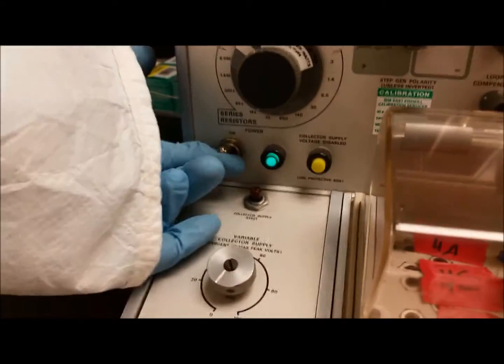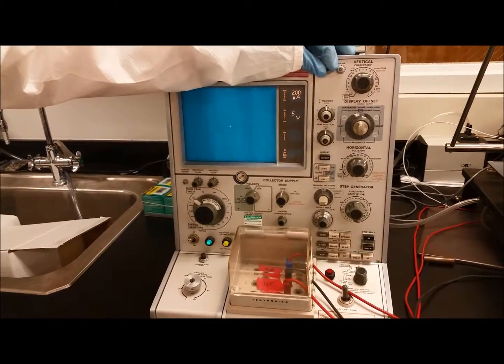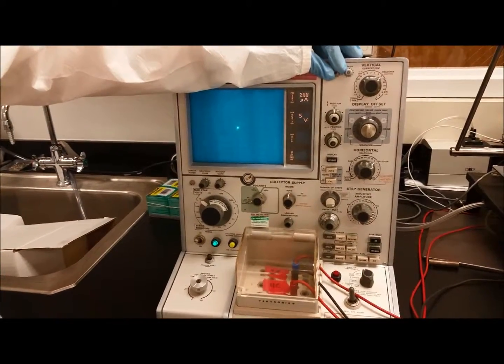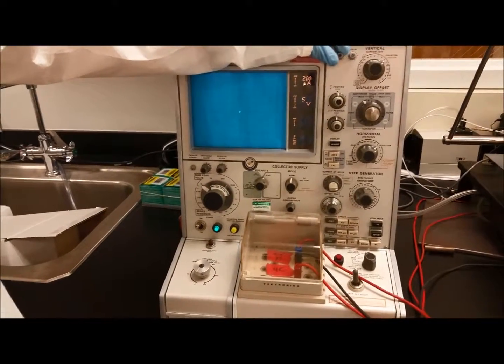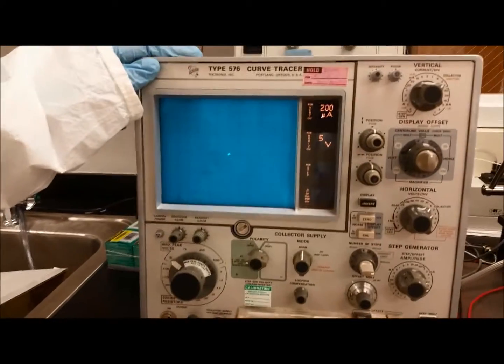Here's our power switch. Light comes on here. And let's zoom out and take a look. Nothing's really happening at first until we adjust the intensity of our scintillating CRT screen. Now, we can damage the screen if we're not careful, so let's make sure that this is just bright enough to see, but not so bright that we damage anything. A general rule of thumb is this brightness is pretty good.